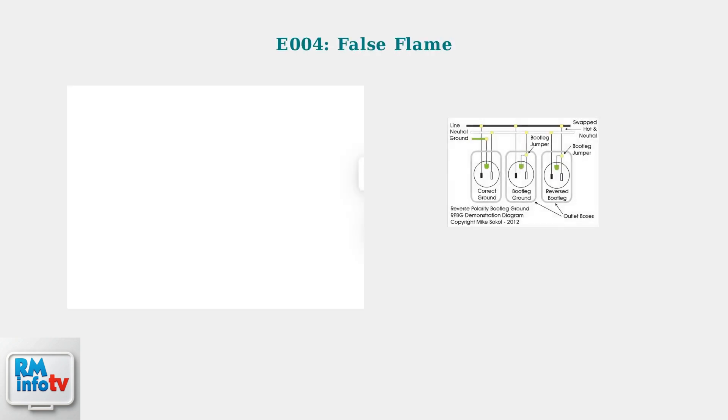Error code E004 indicates a false flame detection. This is typically an electrical grounding issue. Check that your electrical cord is properly grounded and all connections are secure.